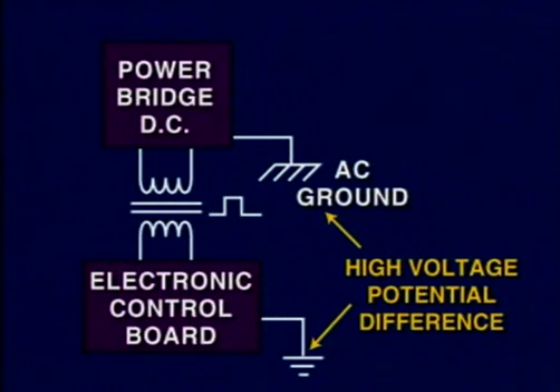Also, be aware that the DC motor control board is isolated from the motor power circuit, and the grounds should never be connected to equipment frame or to the AC ground. This will cause extreme damage to the drive control circuitry.